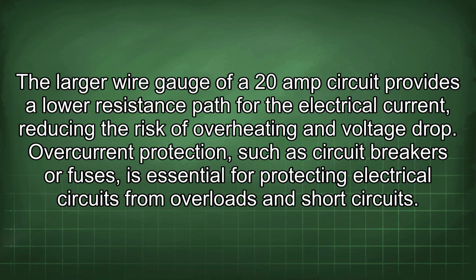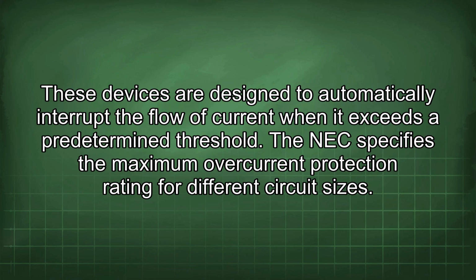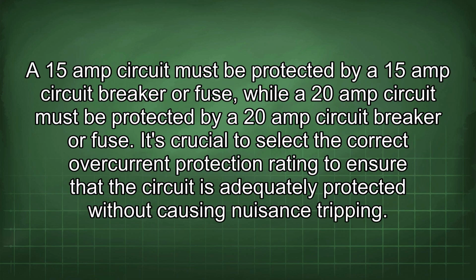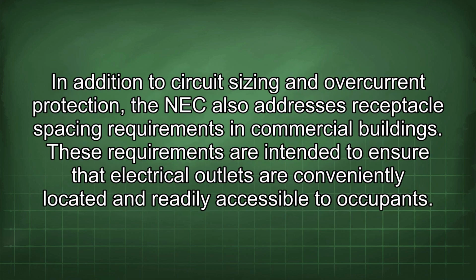Overcurrent protection, such as circuit breakers or fuses, is essential for protecting electrical circuits from overloads and short circuits. These devices are designed to automatically interrupt the flow of current when it exceeds a predetermined threshold. The NEC specifies the maximum overcurrent protection rating for different circuit sizes. A 15-amp circuit must be protected by a 15-amp circuit breaker or fuse, while a 20-amp circuit must be protected by a 20-amp circuit breaker or fuse. It's crucial to select the correct overcurrent protection rating to ensure that the circuit is adequately protected without causing nuisance tripping. In addition to circuit sizing and overcurrent protection, the NEC also addresses receptacle spacing requirements in commercial buildings.